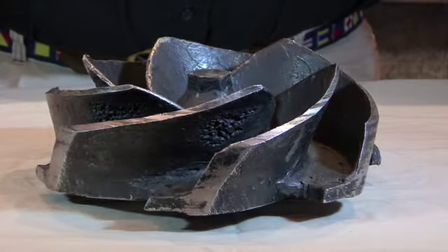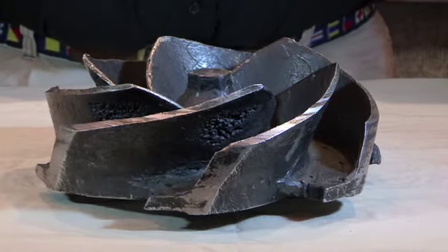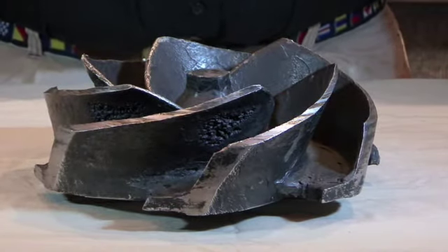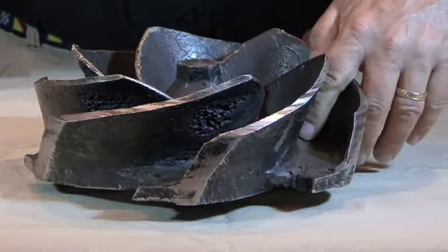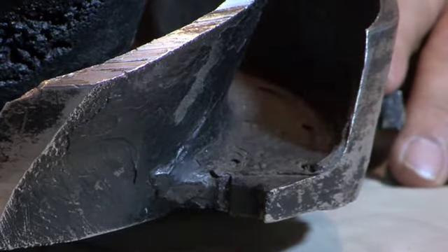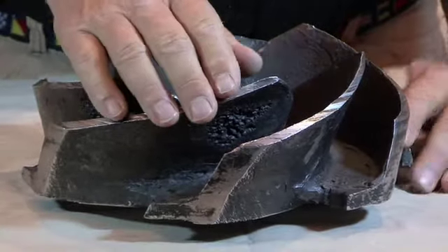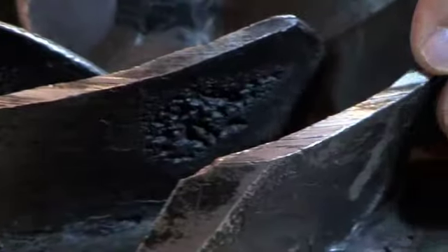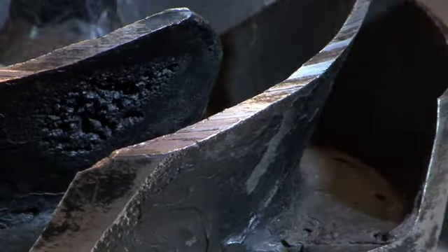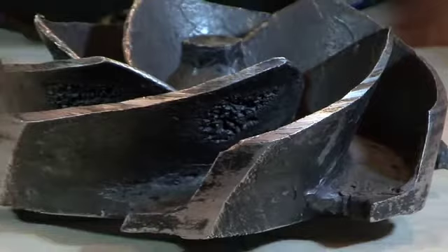As we start to inspect impellers, the first thing we need to look at is the general and overall condition of the impeller. As I look at this particular impeller, one thing that stands out almost immediately is the fact that it has a coating of black material on it. And if we look up and down here in the ways, you can see there's a fair amount of material built up there. That would throw the impeller out of balance for sure. Another feature that we note is that when we look at the ends of the blades right here, particularly over here, you can see that there are deep score marks in the impeller. This indicates that this particular impeller was in contact with the casing of the machine, and this caused damage.